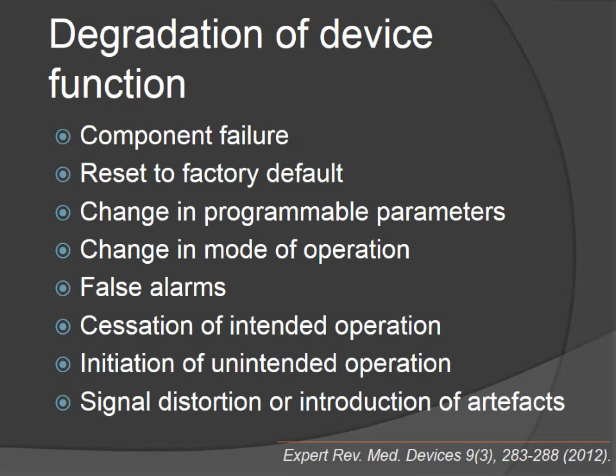So what happens to our devices? We can have individual components that fail. We can have a reset of the device to some factory mode for initial programming. We can have changes in the programmable parameters, or a change in the mode of operation. We can have false alarms, which should not be underestimated, because those still frighten patients tremendously and make them very nervous about their device, leading to frequent hospital visits. The device can also stop working the way it's intended, or start working in a way that is unintended.